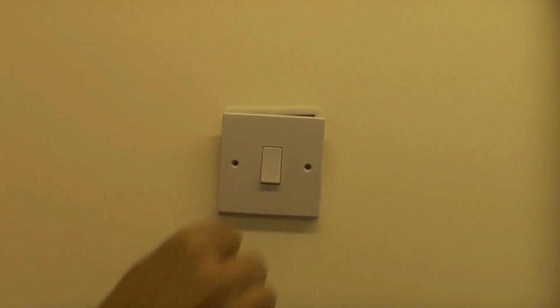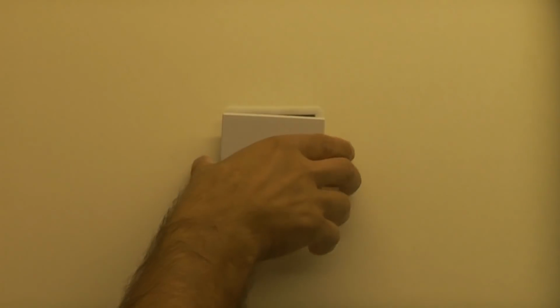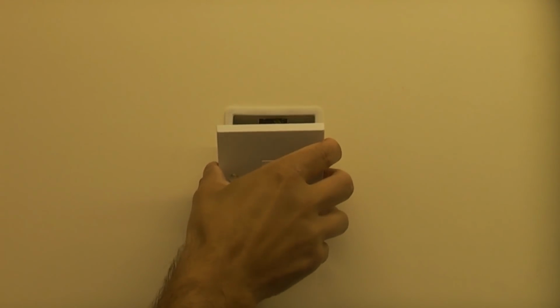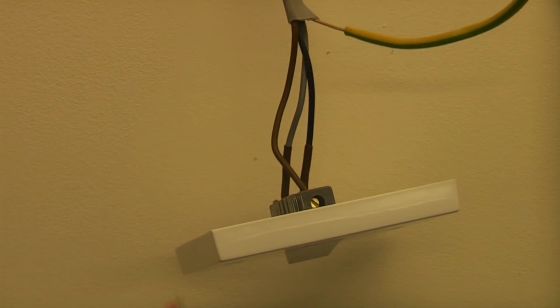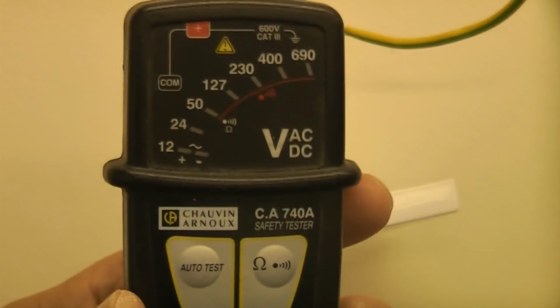So we've now isolated the electric. We're now going to remove the screws. And then we're just going to pull that forwards. I'm now going to carefully expose the earth wire. I'm now going to use an approved voltage tester to test that this is dead before we touch any of the terminals.